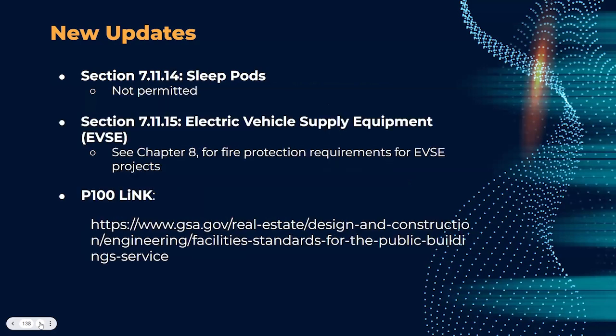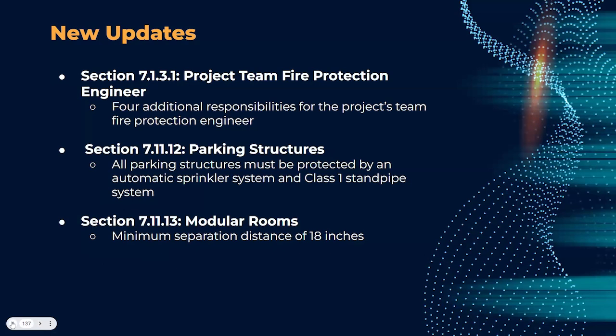The third update is a new section on modular rooms, added to address new hazards associated with modular rooms now being installed within our buildings. The new requirements address sprinkler protection, fire alarm system audibility, egress reliability, and a minimum separation distance of 18 inches between each modular unit.